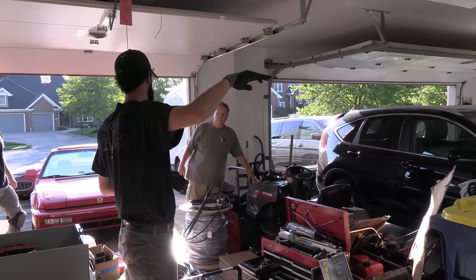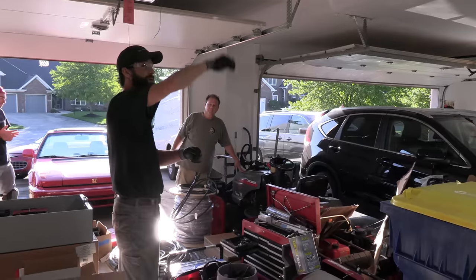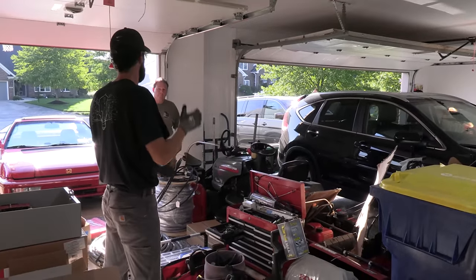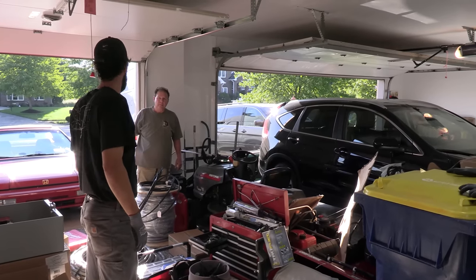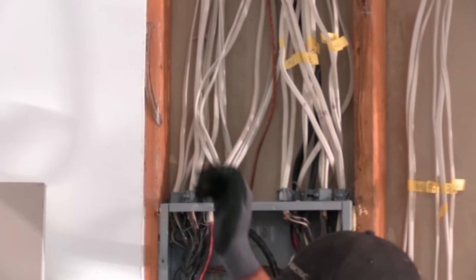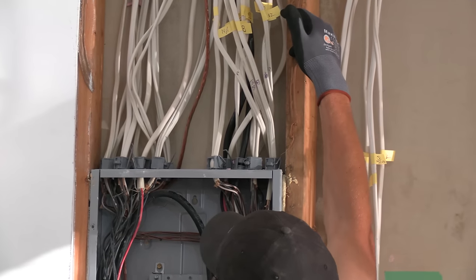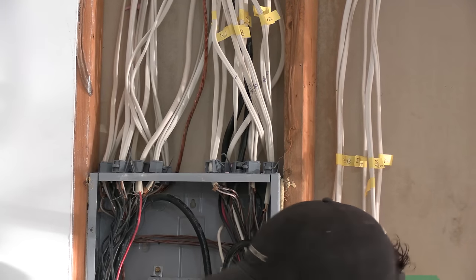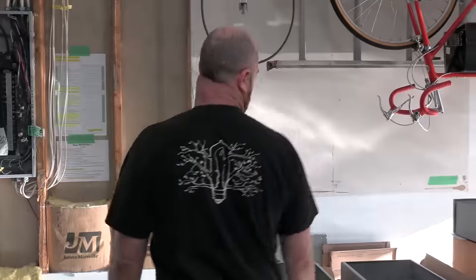Here's what I think we'll do on our wire runs: set up the wire spool here in the garage, pull down through the basement the longest portion first, then peel them off to length and cut them. Pull the final portion as opposed to trying to fight the up-over-down-and-through all in one pull. When we're bringing the wires in, no crisscross — we're going to take pains, straighten everything out, flatten it up and make it beautiful. We'll slip a two-by-four block in there 12 inches or so above the top of the panel so we can staple everything flat. We'll also use nail plates — one nail plate above each panel — and I've got a third one I might use over there.